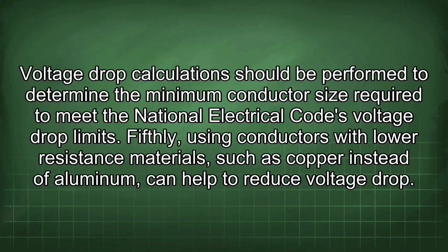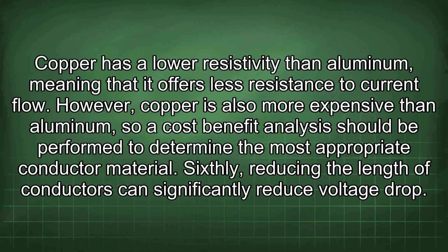Fifthly, using conductors with lower resistance materials, such as copper instead of aluminum, can help to reduce voltage drop. Copper has a lower resistivity than aluminum, meaning that it offers less resistance to current flow. However, copper is also more expensive than aluminum, so a cost-benefit analysis should be performed to determine the most appropriate conductor material.